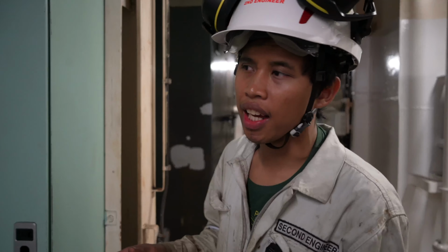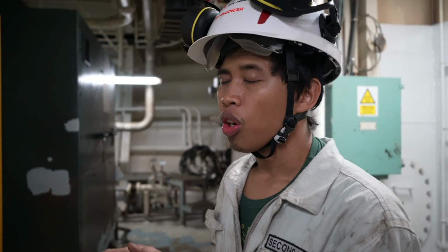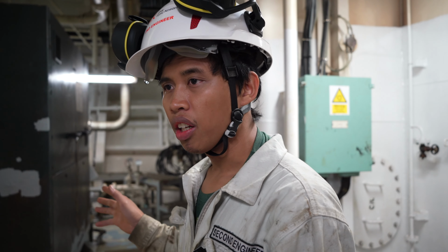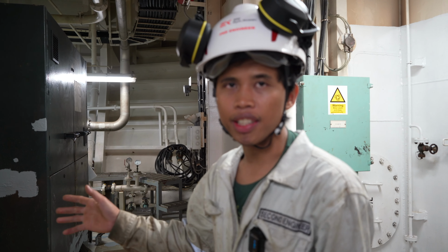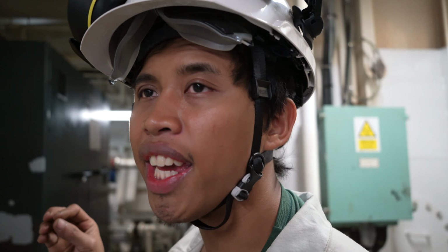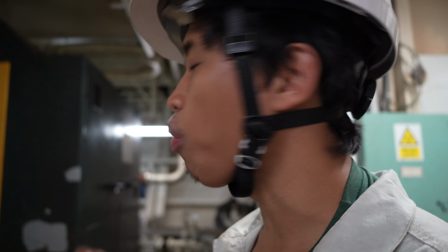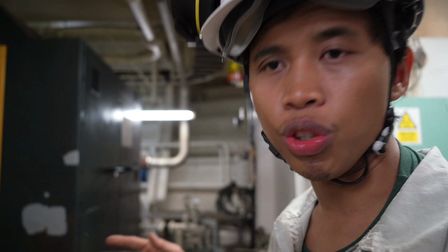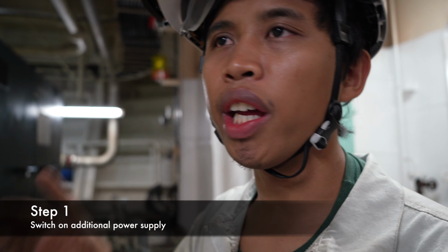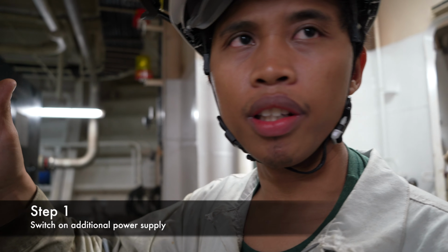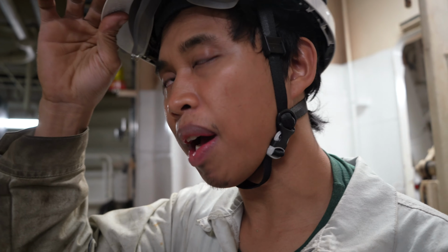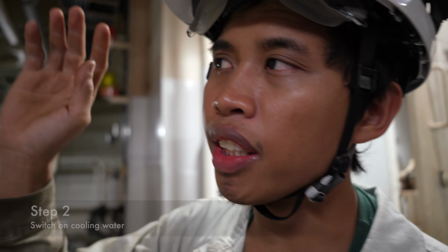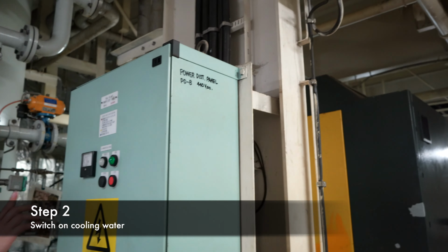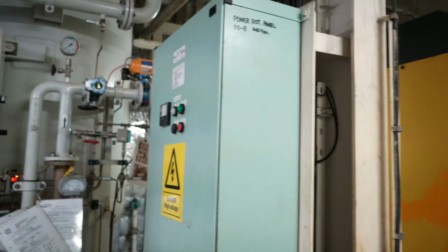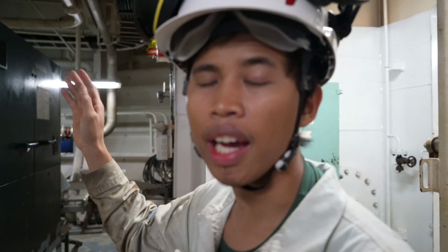Once the cooling is running, we can now start the compressor. But first, open the vents to release any stored air in the system, so the compressor will not have a hard time building up pressure. So what is the first step? Step number one is power, additional power. Second step is cooling water. Switch on cooling water. This is for the compressor and for the refrigerant dryer.